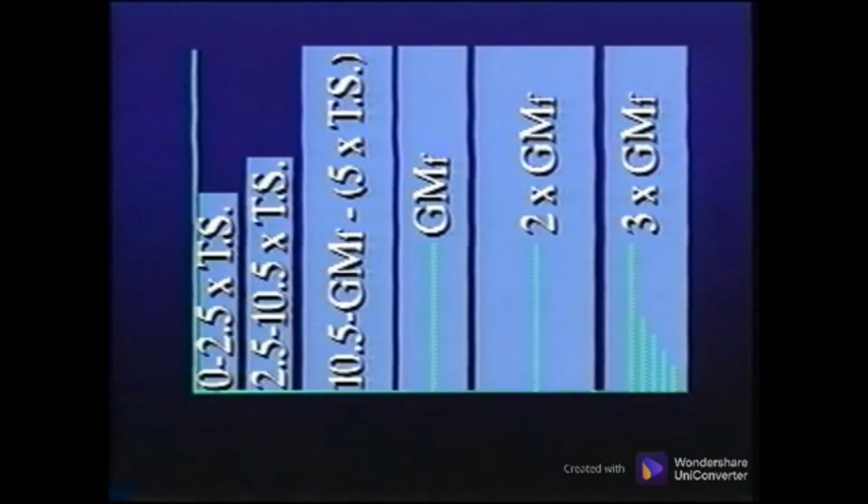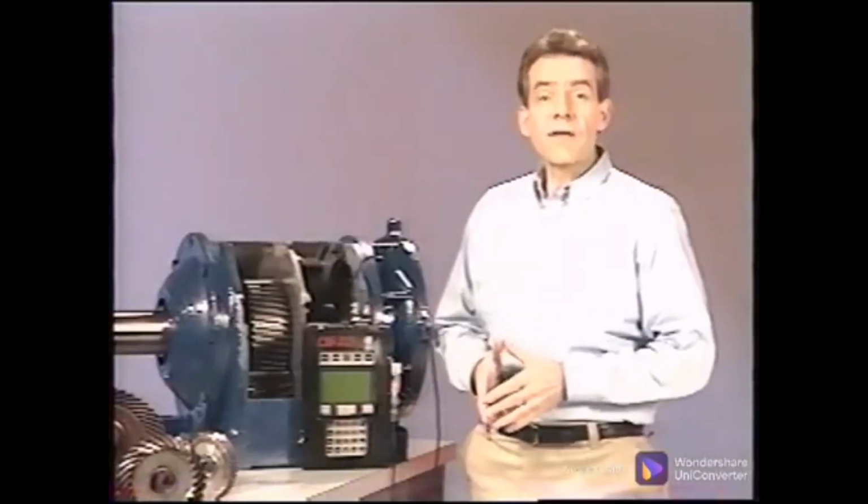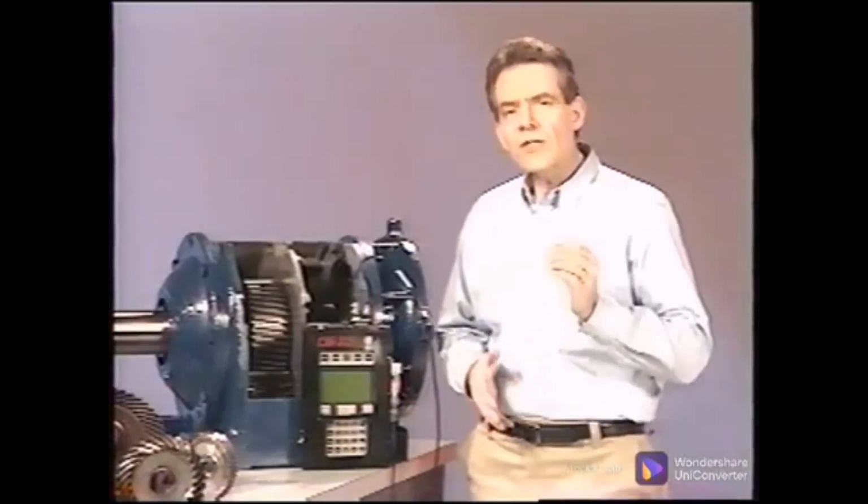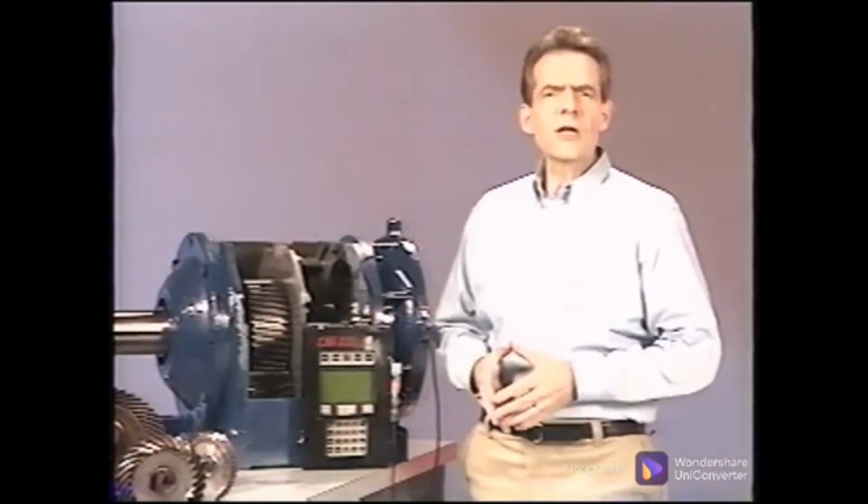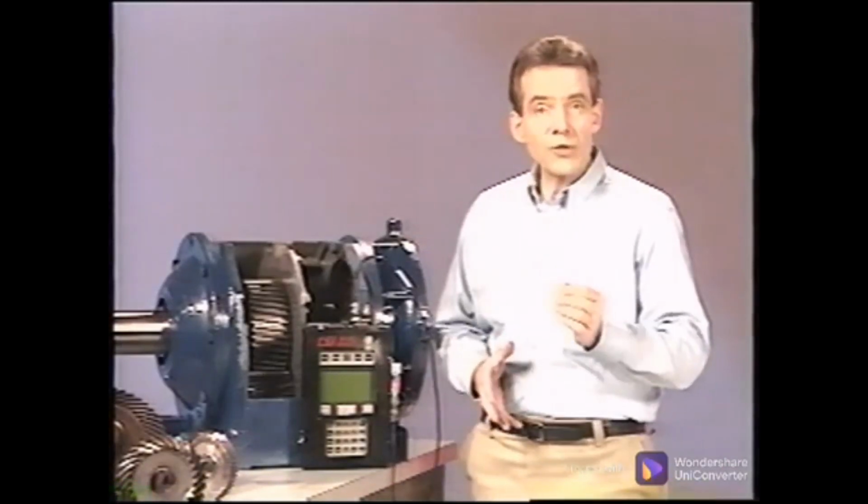The sixth band should include all the energy from here to the Fmax and will include the area around 3x gear mesh frequency. Some analysts define these last three bands in units of acceleration because the gear mesh frequencies can generate large amounts of force, and acceleration is a direct measure of force.